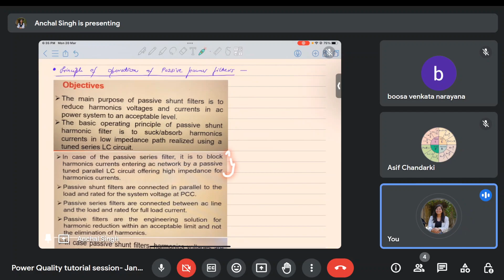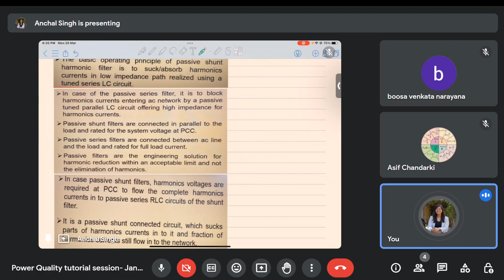So passive filters are the engineering solution for harmonic reduction within an acceptable limit. They will only reduce; they cannot eliminate. Why is that? Because our system does not always operate at a fixed operating point. The operating point keeps changing with time. So when we are providing a fixed kind of solution to a variable kind of problem, it can only reduce to an extent. It cannot completely eliminate. If you want to completely eliminate, you will have to go for active compensation.